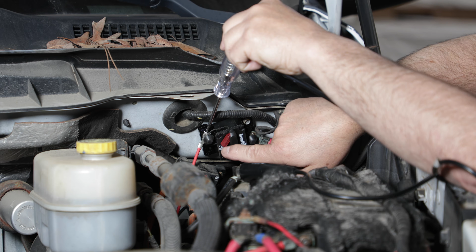What we're going to do is check power to the circuit breaker using the test light. First I check the test light to make sure it's working properly, then check on one side and the other, so I can tell the power is actually working for the circuit breaker. If it gets popped, the light goes off, then I reset it. That's how you check the circuit breaker, to make sure it's working and getting power to the controller.